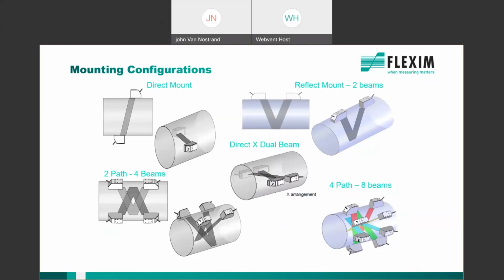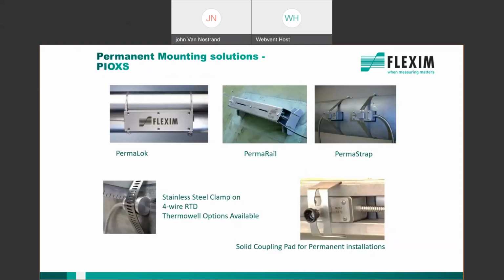And we can also use a couple of different styles of mounting. We can use direct mount, which typically requires the 10 and 5 diameters. Then reflect mount would require fewer diameters. And then if we used dual beam, meaning 2 sets of transducers averaging, or even 4 sets averaging, we can improve the accuracy greatly without that straight run.